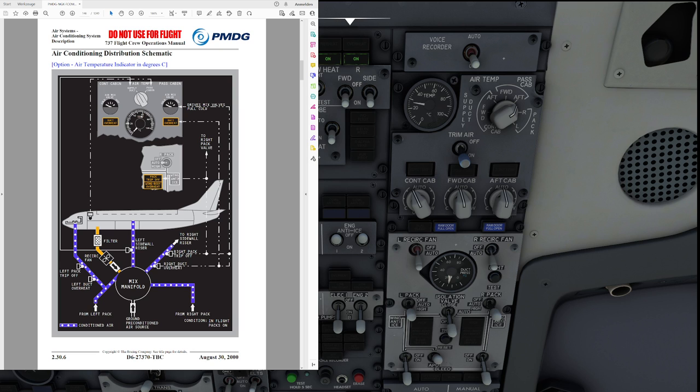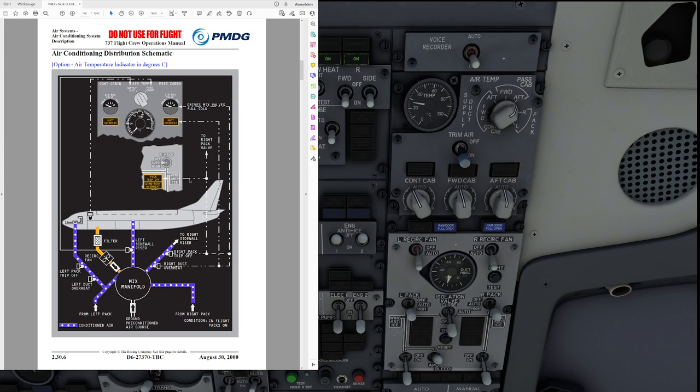On the left hand side here we see the air conditioning distribution schematic for the Boeing 737-600 and 700 as you have seen them already in Microsoft Flight Simulator. Now, you can see that we have the mix manifold with air from the left pack going right to the flight deck into the mix manifold, same from the right pack and then this is distributed to the left and right sidewall risers.